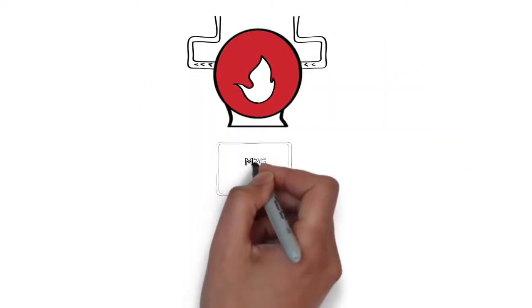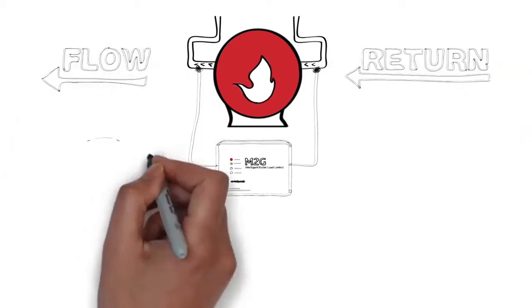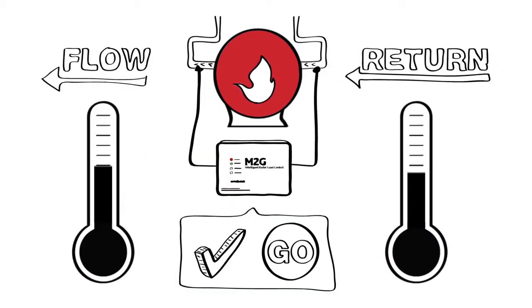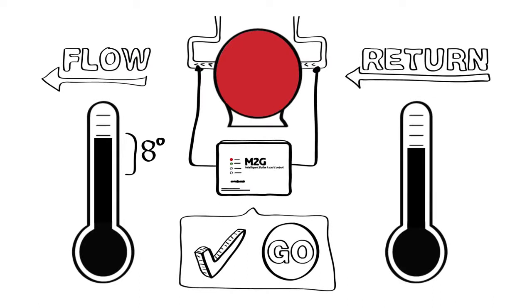M2G does this by measuring the boiler's temperature as the water flows out of the boiler and as it returns. As the boiler reaches its required temperature M2G takes a snapshot reading of the flow and return. From these readings M2G applies an 8 degrees dead band on the flow and a 3 degrees dead band on the return.